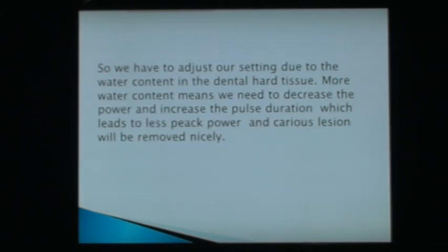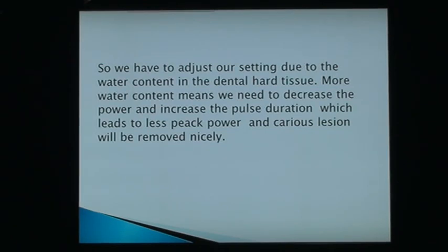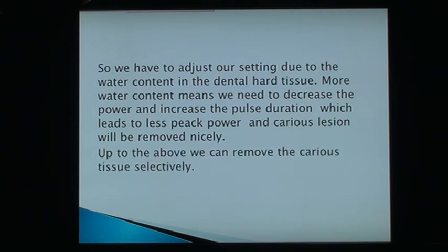Here we can understand that if we have caries dentine, that means we have more water content. And if we have more water content, we will have good ablation by using erbium or erbium chromium. We summarize this and say, we have to adjust our setting due to the water content in the dental hard tissue. More water content means we need to decrease the power and increase the pulse duration, which leads to less peak power, and caries lesion will be removed nicely. Up to the above, we can remove the caries tissue selectively.